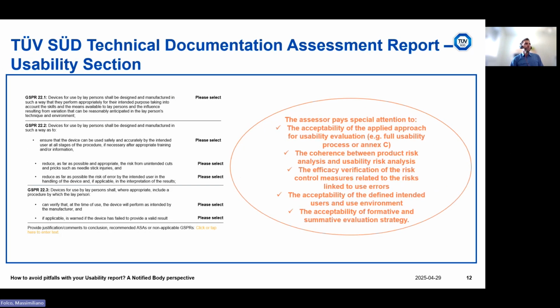Then the assessor pays special attention to the acceptability of the applied approach for usability evaluation, for example, full usability process or Annex C. We have other slides about this topic later on. The coherence between product risk analysis and usability risk analysis. Product risk analysis follows ISO 14971, and usability risk analysis follows IEC 62366. Actually, usability risk analysis is a part of product risk analysis.